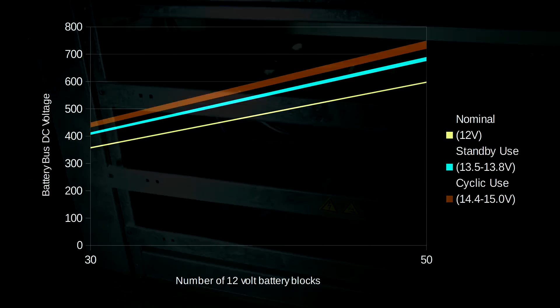But it would still pack a lot of punch if I connected them all in series and accidentally got a belt off them. I mean, 46 batteries, you're getting not far off London Underground train voltage if those things are fully charged. So I have no intention of killing myself with a set of duff batteries. So I'm not going to be testing this one in its capacity as a UPS at least. And for that reason, could you really consider this one for load shifting? Well, if you could get hold of cheap batteries, then yes.